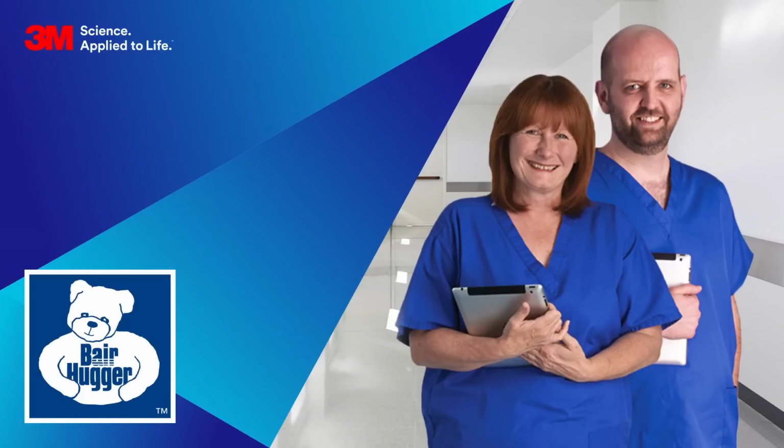Helen, are there any contraindications for the underbody range? There are two that you have to be aware of. If you've got an area of the patient that has no blood supply, for instance, if you've cross-clamped the aorta or they have an embolus, then you don't want to actively warm that area of your patient. You can still use the Bair Hugger to warm the rest of that patient, but while it's cross-clamped or while you have no blood supply, you don't want to be warming that area.